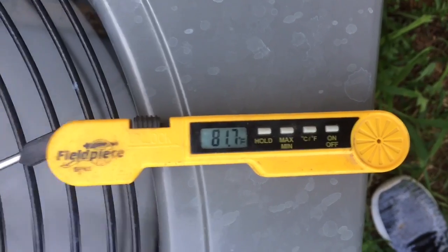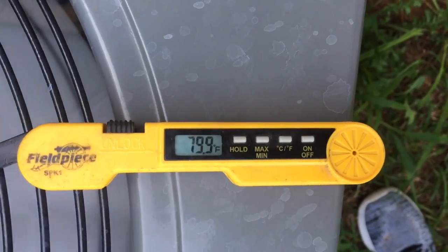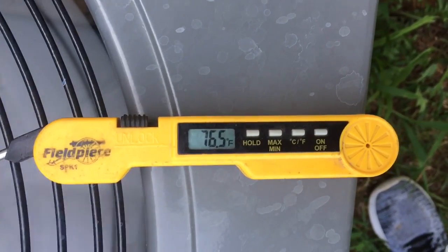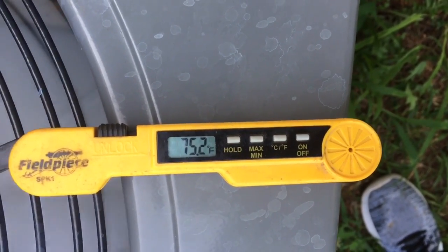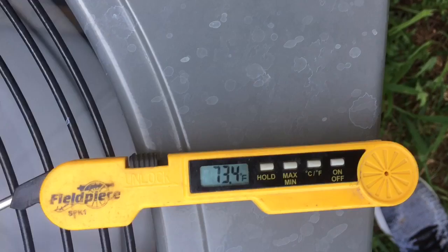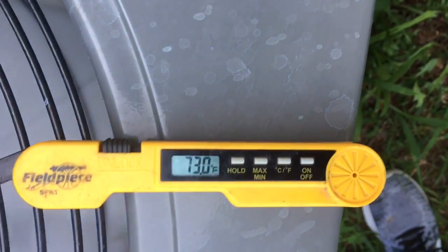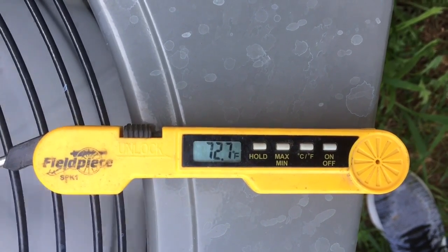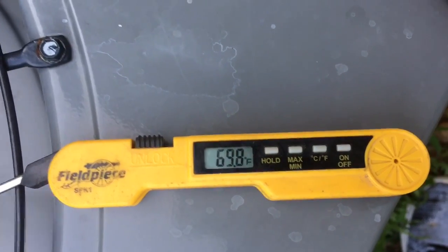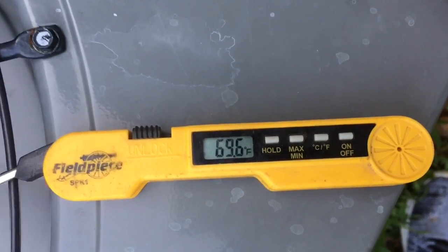We see a drastic drop in that pretty quickly. So like I said, in order for it to absorb heat, it has to be operating a little bit colder than the temperature of the air around it. We've already passed our 10-degree mark. We said about 86 going in, and we've got about 69, 70 degrees coming out. Now it really is getting close to 60.